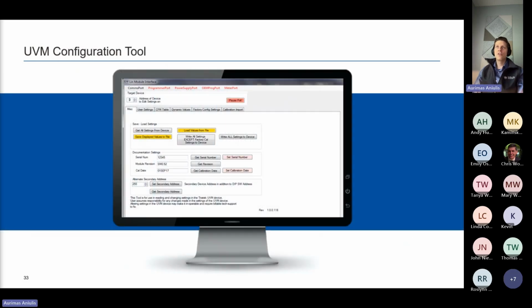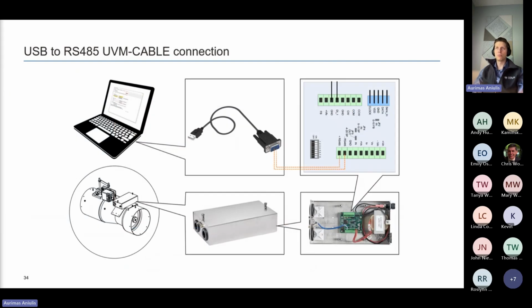There is a UVM configuration tool that is required to do any kind of field K-factor setting, adjustments, or to pull some data, or when we're troubleshooting, manual overrides, et cetera. That tool is free and comes installed on your PC. You get a USB to RS-485 cable, and it connects to the side of our enclosure on the valve. At that point, you can communicate with the device and perform any sequence of operations that you'd like.